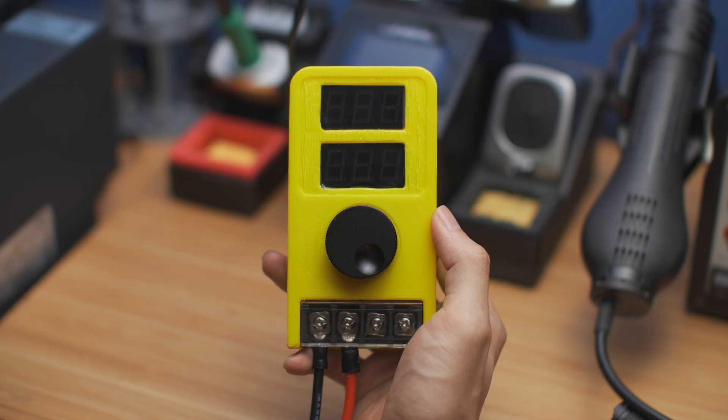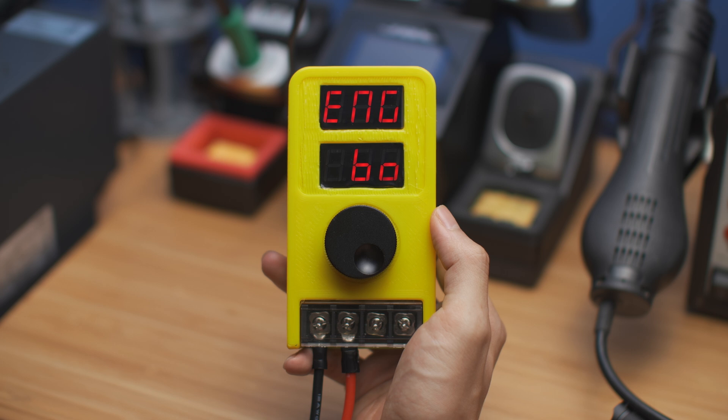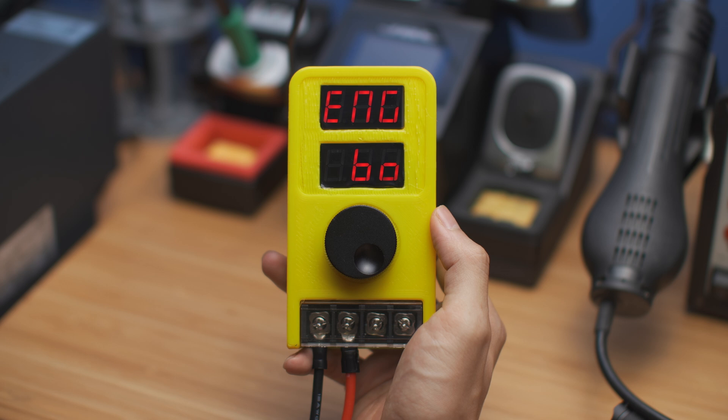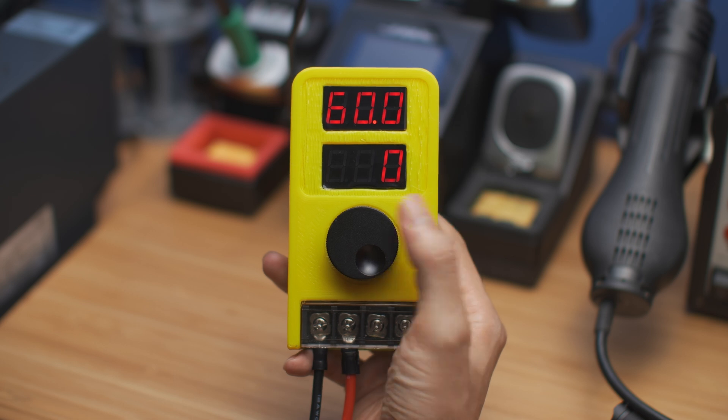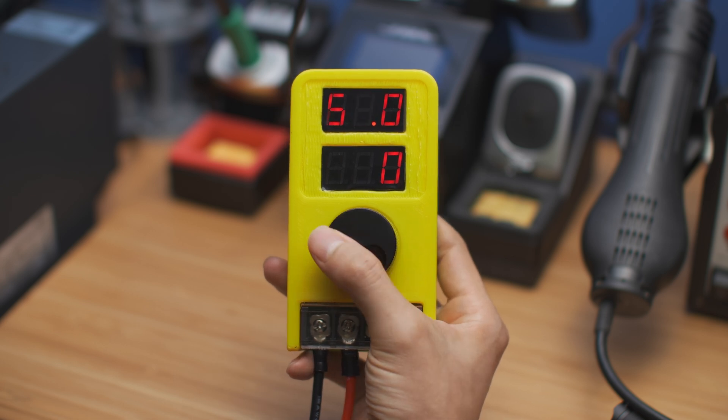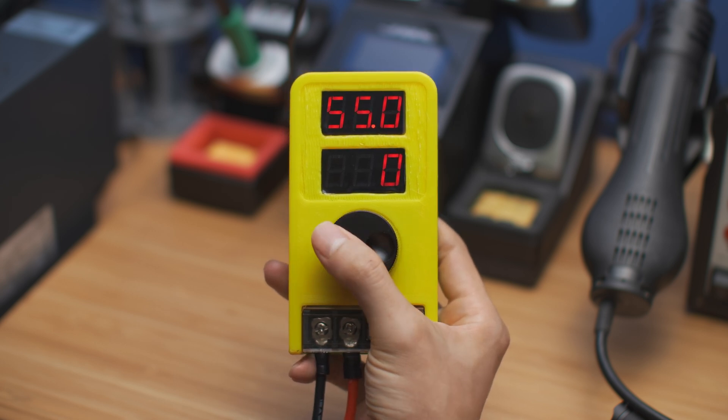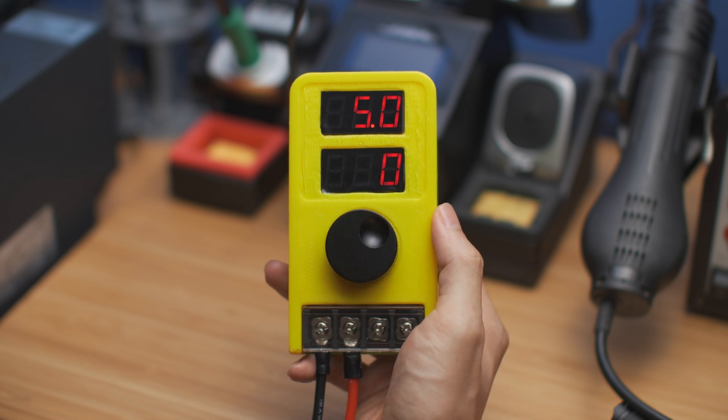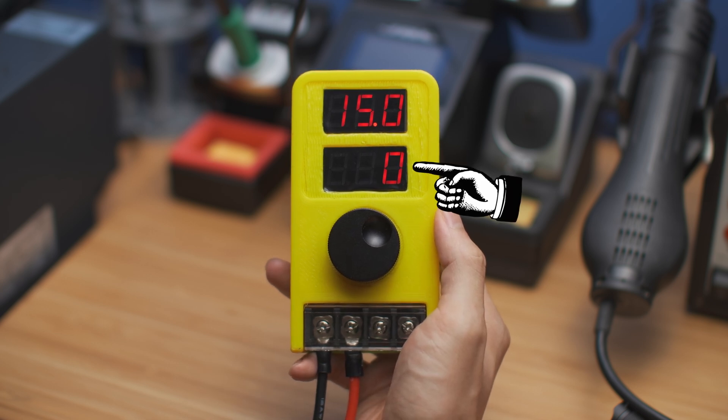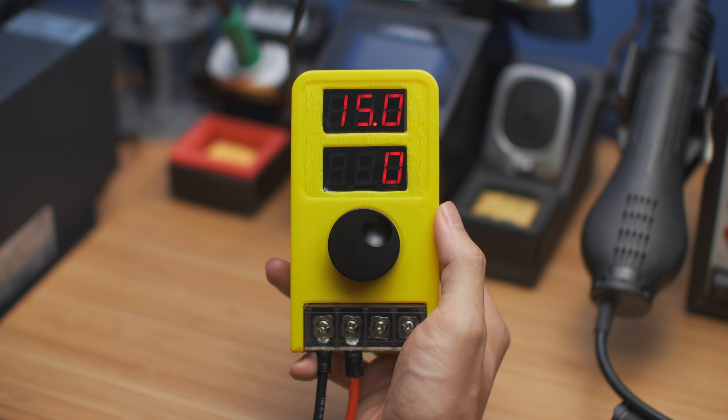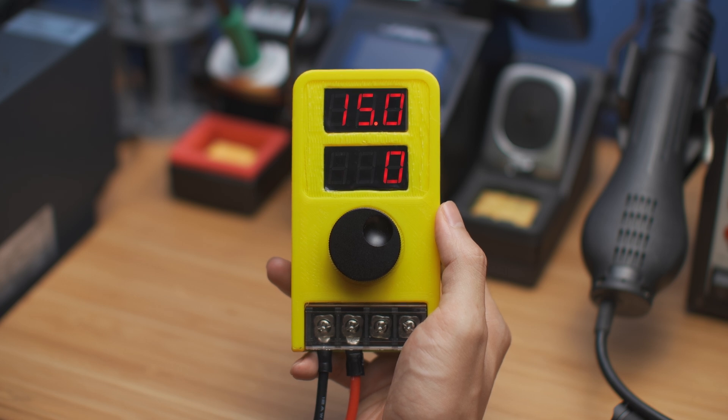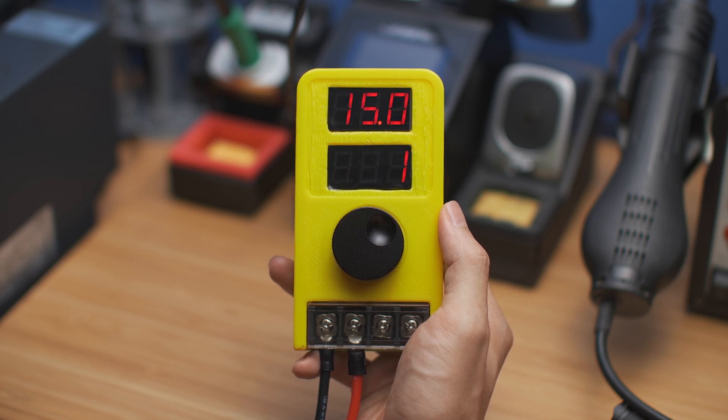Let's take a tour of the device. It's powered through this screw terminal block, and can handle voltages between 12V and 60V. The input power is passed through, so downstream devices can be connected here. The top display shows the overvoltage threshold, which we can adjust by depressing and using the knob. The bottom display shows the number of overvoltage events since startup, which is useful for finding out if any unexpected voltage spikes are happening.